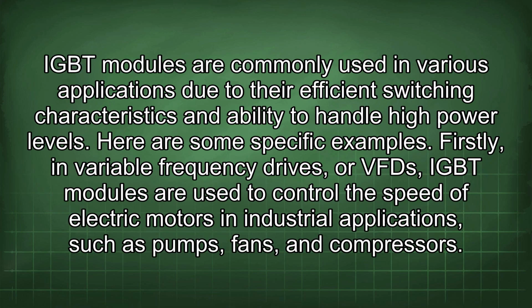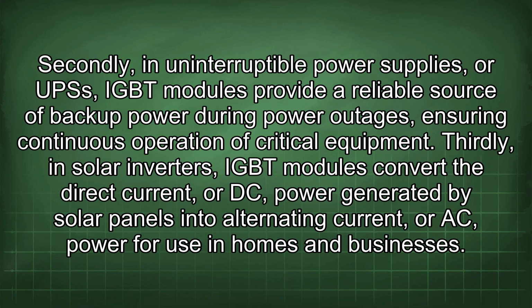IGBT modules are commonly used in various applications due to their efficient switching characteristics and ability to handle high power levels. Here are some specific examples. Firstly, in variable frequency drives, or VFDs, IGBT modules are used to control the speed of electric motors in industrial applications such as pumps, fans, and compressors. Secondly, in uninterruptible power supplies, or UPSs, IGBT modules provide a reliable source of backup power during power outages, ensuring continuous operation of critical equipment.